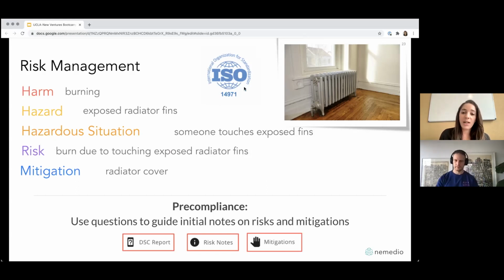And so from a 14971-compliant risk management perspective, you are basically decomposing that risk sentence into its constituent parts and analyzing the likelihood that those result in the patient getting hurt, or the person using your medical device getting hurt. This activity needs to be done for each risk that exists with your medical device. So it's a very systematic, very long approach in order to identify every single risk about your device. So now that you have this long list of risks, you might ask yourself, why would FDA ever let my device get cleared if it's so risky to use? Somebody could get electrocuted by touching a wire, or somebody might get their finger stuck in this moving part.